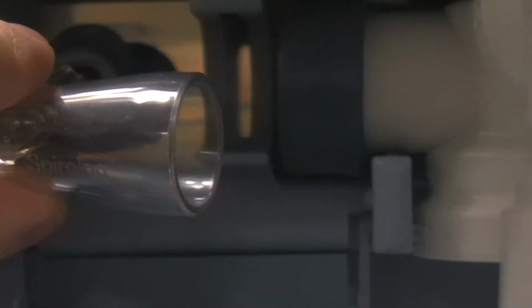Now another piece of that puzzle is where the flow transducer is located. The flow transducer is located right behind this door. If you push down on that, that's where the flow transducer is, and the flow transducer is that clear tube that you see right over there. To successfully remove this without breaking it, you need to slide this over to the left like that and then pull it out. When you're putting it back in, say it's a brand new flow transducer, line it up. You can see it's got that configuration right over there, and this pin configuration.